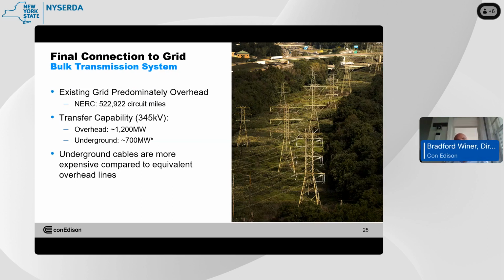The first is that overhead connections typically provide more transfer capability. If you compare this to our 345 system, you get about, for the purpose of this conversation, 1,200 megawatts of transfer versus underground, which will be about 700 megawatts. The challenge is that 700 megawatts is going to change—it'll be impacted by environmental conditions, meaning you'll ultimately need more circuits to transmit the same amount of power. So in this example, 2 345 kV circuits are needed to transmit the output of that converter station and get it into the electric grid.